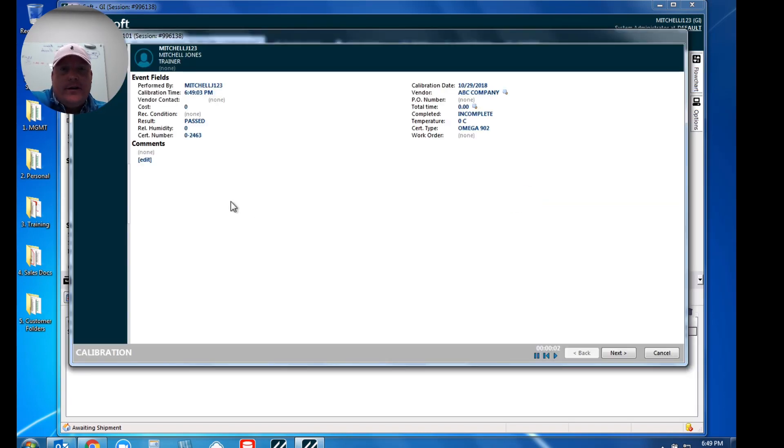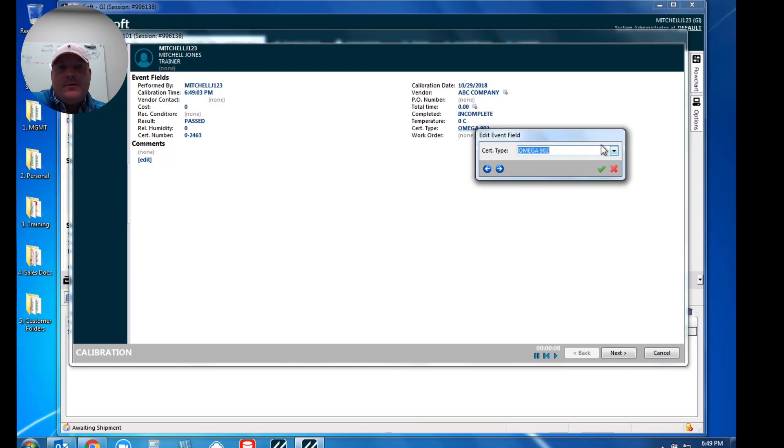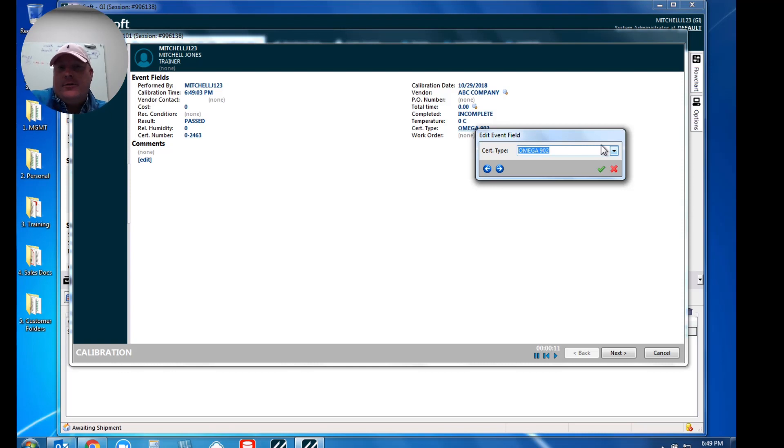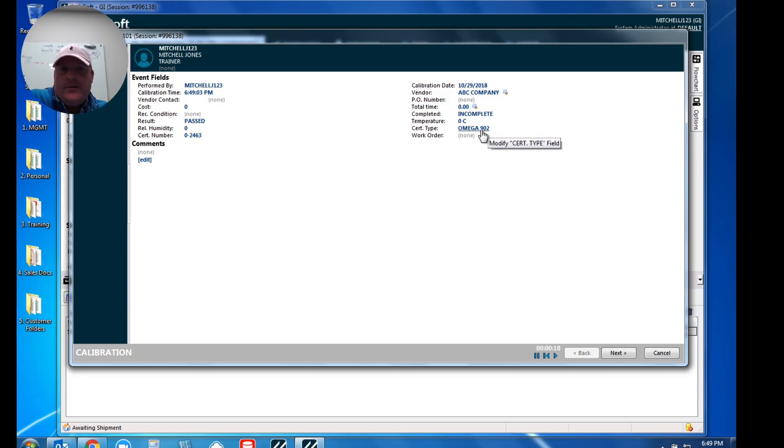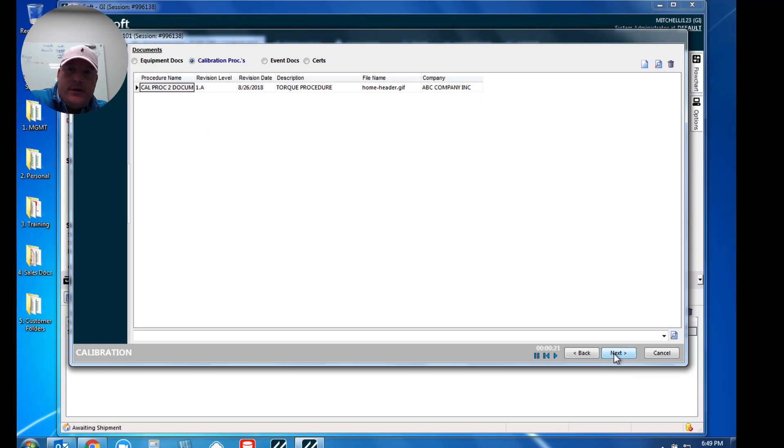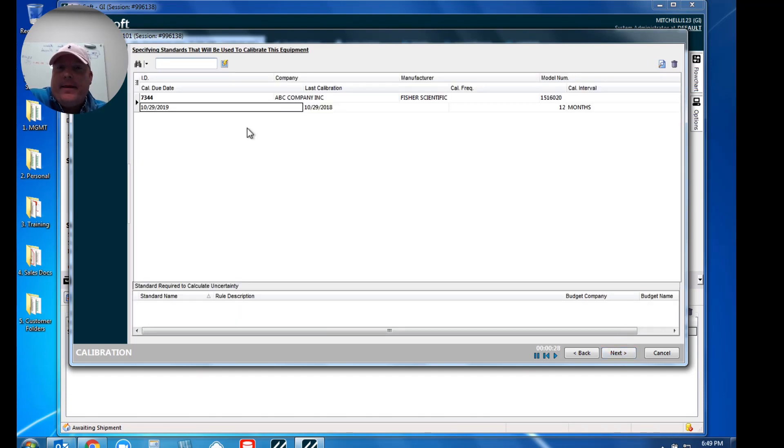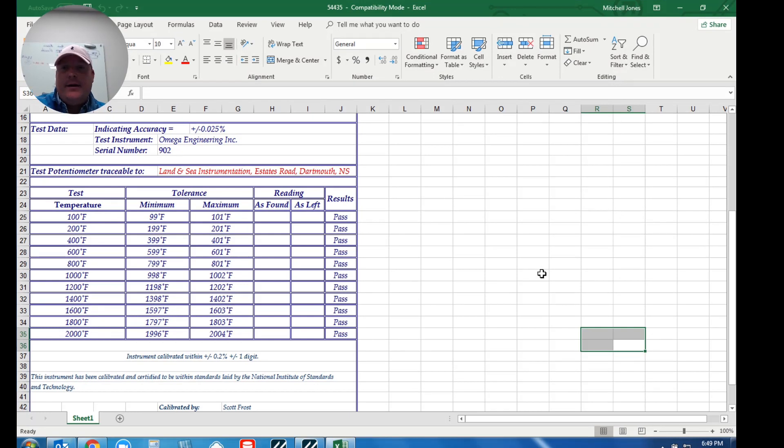Let's say I've got my instrument and I'm ready to perform a calibration. What I'm going to do is just execute my calibration event. We all know inside of here you kind of have your who, what, when, where. But I want to point out our certificate type. I have a very specific certificate type set up here for my Omega 902, that way it just matches that Excel file that I'm utilizing. So this is an important step to notate that. As we proceed through, those are calibration procedures with revision control, any applicable charges or discounts this customer may have. Of course I've got my standard that I'm utilizing.